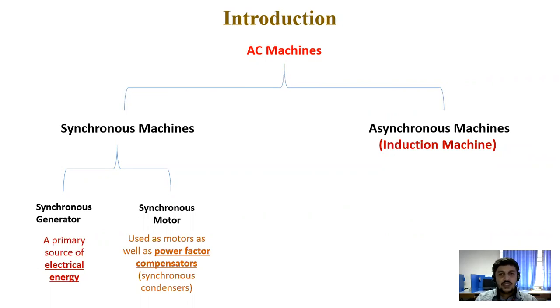Whenever an overexcited synchronous machine is connected in a system, it is a source of reactive power. So an overexcited synchronous machine always operates as a power factor compensator. This is a well-known application of a synchronous motor, as a power factor compensation device, generally termed a synchronous condenser.